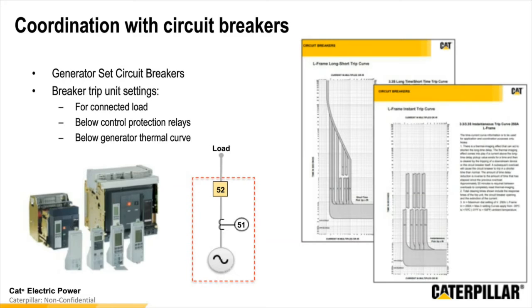So with the breakers themselves, the breaker is the physical device that's doing the opening and closing of the path of power. But the breaker itself then has a trip unit that will be part of the breaker that will be doing the monitoring and will really be making the decisions on when to open or close the breaker. There are different types of trip units available. Typically, there's the LS, which is a long and short time trip. There's the LSI, which is a long, short, and instantaneous trip. And there's the LSIG, which is a long, short, instantaneous, and ground fault trip.